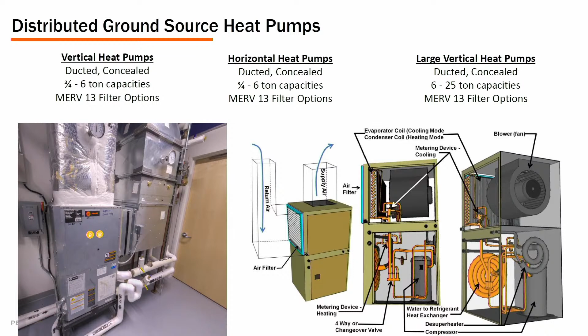The function that those have is space temperature control, and they're independent of the fresh air system, which operates differently. So if the fresh air system fails or shuts off, you still heat and cool your building with this. It has nothing to do with that, so it keeps it independent. Whereas on the system at Marathon, if you lose one rooftop unit, you've lost heating, air conditioning, ventilation, the whole nine yards. And if you lose one heat pump, you've lost one or two classrooms instead of a whole wing of a building. So there are some other pros and cons that come along with that.